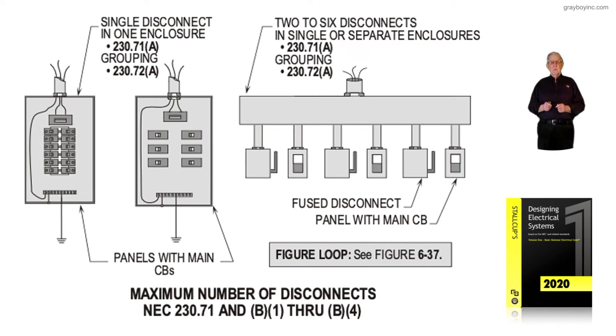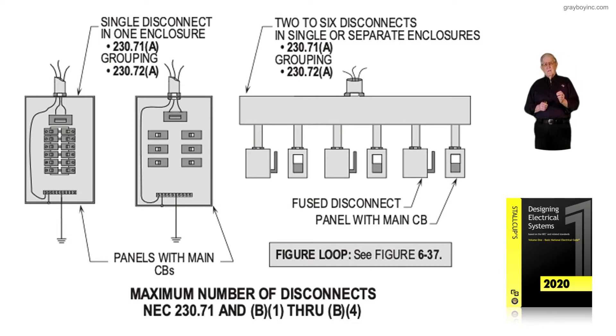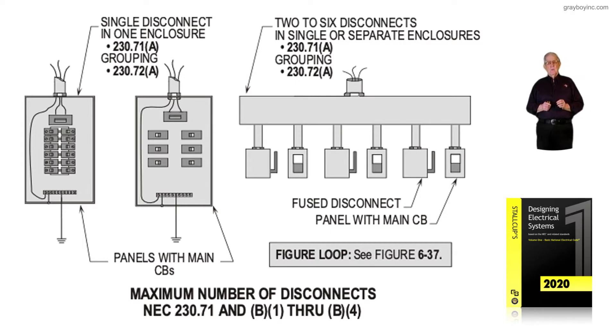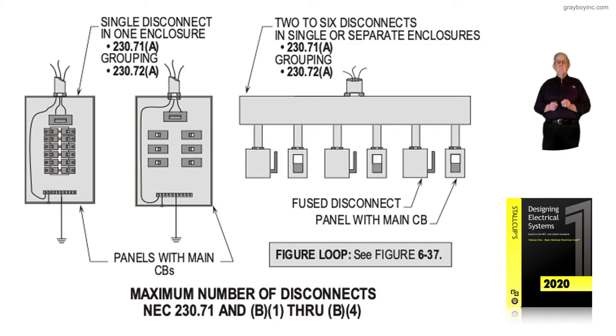This illustration deals with the maximum number of disconnects, and notice this is a new rule in the 2020 NEC. This was not so in the 2017 edition. The maximum number of disconnects at a service by NEC 230.71 is 2 to 6. Notice we have 230.71 B1 through B4 — there's the big change.